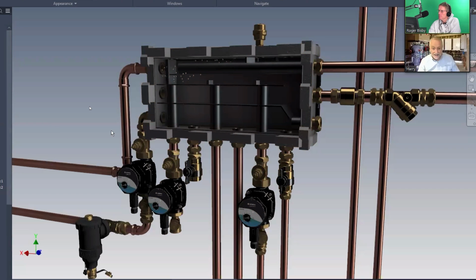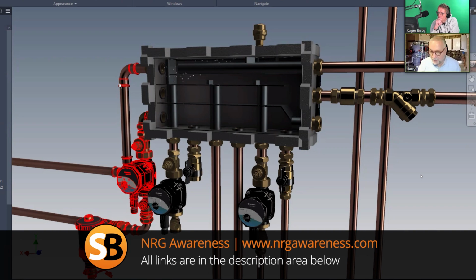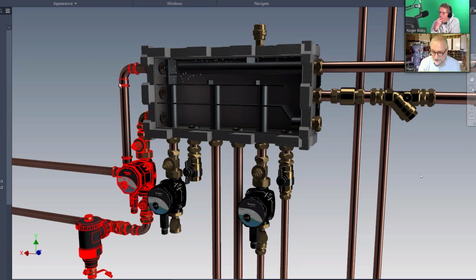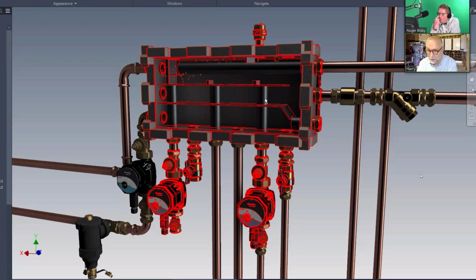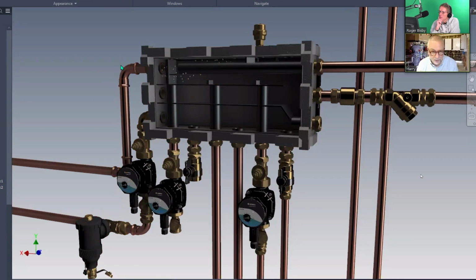The heat pump has to get its heat out from the boiler, and when it does, nothing should stop that flow. If it stops the flow, the heat pump can have issues with the compressor overheating or the refrigerant overheating, with parts going wrong. That's why heat pump manufacturers are constantly saying you should put in buffers and volumizers. Sometimes you need a volumizer depending on the size of the system and the size of the heat pump. But normally, if I have an empty iron box and I put water in and take water out, there's very little technically to go wrong with that.